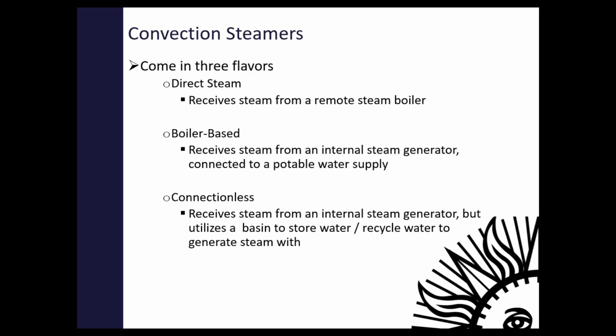So you're running a very low load on that boiler, most likely in the summer, wasting large amounts of energy there, as well as water through that system, because you're probably not returning a ton of condensate back to your boiler. Another system is the boiler based. It has an internal steam generator. You just connect a water supply to it, and it will generate the steam. Steam flashes into your cooking area, heats your food, and then will go down to your storm drain rather.